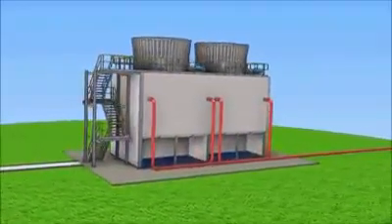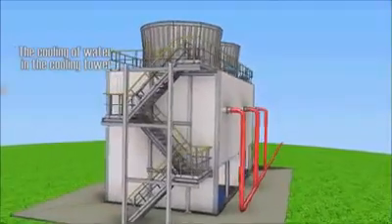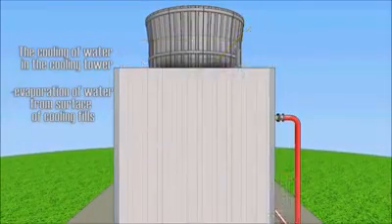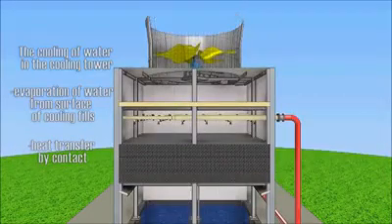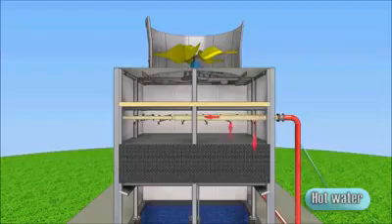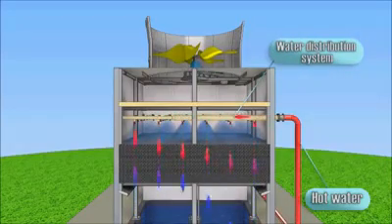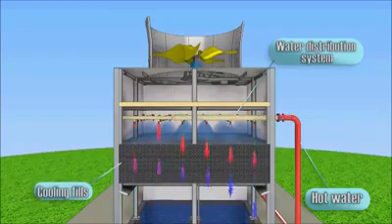So, how does the cooling tower work? Water in cooling towers is cooled by evaporation of water in the stream of atmospheric air, the heat transfer happening by contact with air. Hot water from various sources such as machines or heating processes flows through pipes to the distribution system of the cooling tower, which distributes the water evenly to all the area of the fills by the spray nozzles.